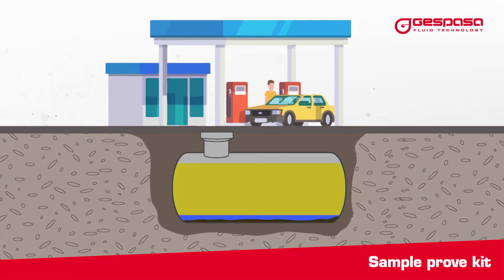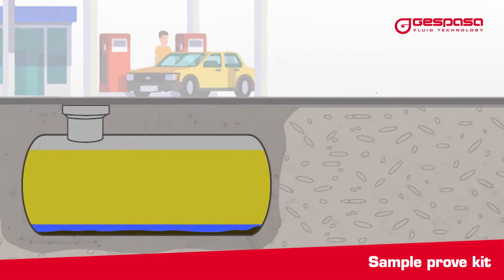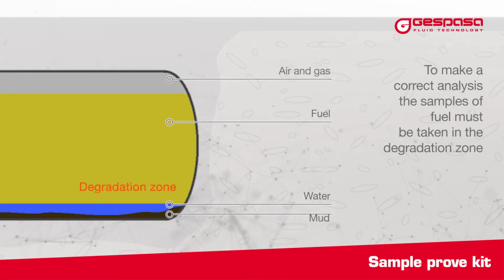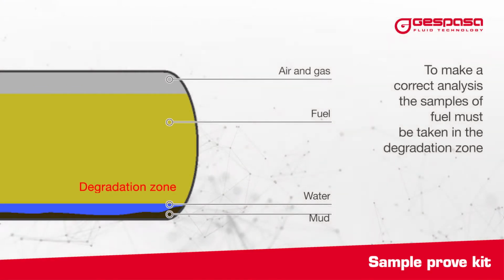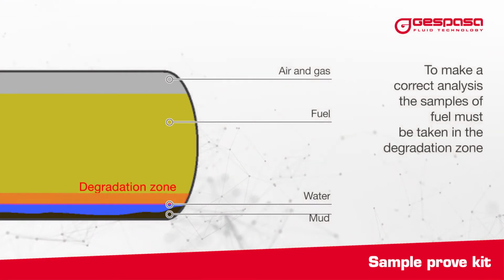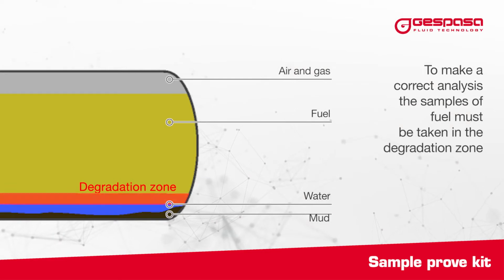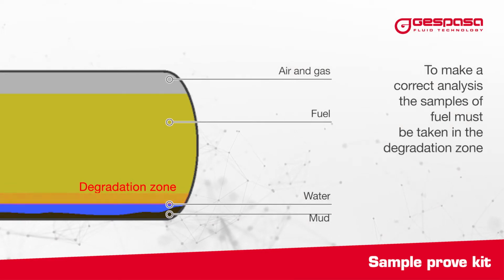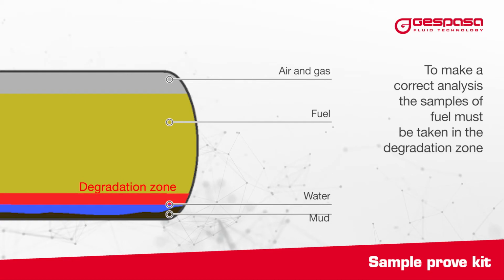To perform a fuel analysis, you must take a sample of the fluid located at the bottom of the tank, just above the sludge and water. This area is called the degradation zone. Bacteria begin to grow in the degradation zone, and it's the area in which the fuel begins to deteriorate its properties.